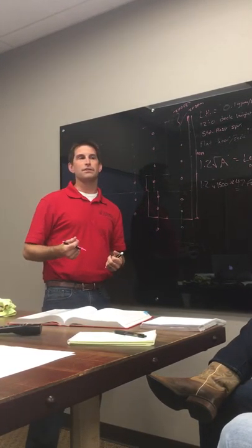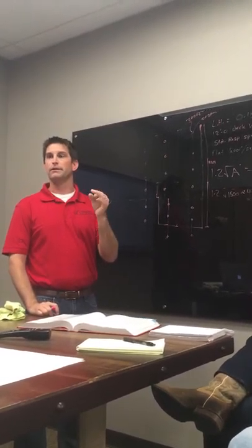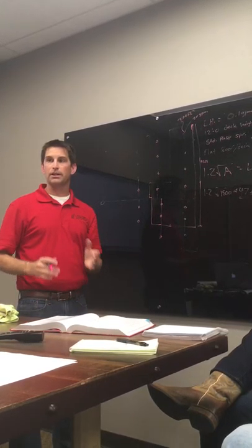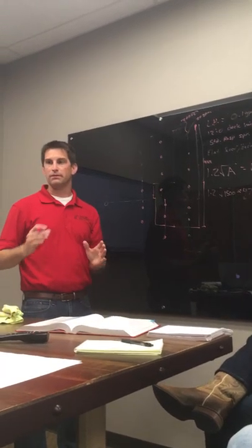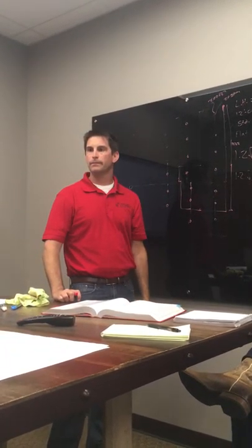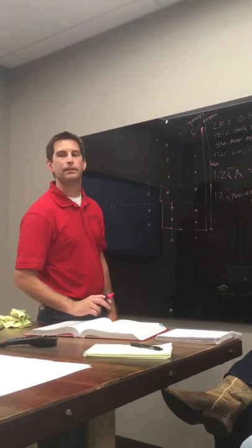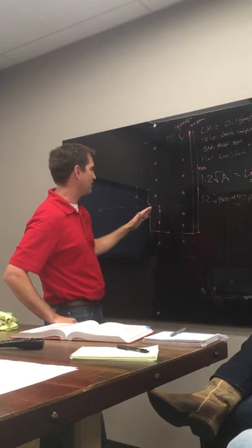K factor is just a coefficient that represents how big of an orifice, how big a hole, the water is spraying out of when the sprinkler opens. Typically it's going to be half inch up to three-quarters of an inch. They're pretty small, most normal sprinklers. So the K factor is proportional to the size of the orifice that the water is coming out of? Yeah. Okay, so don't get too hung up. We're not going over that. I just want you to understand why.